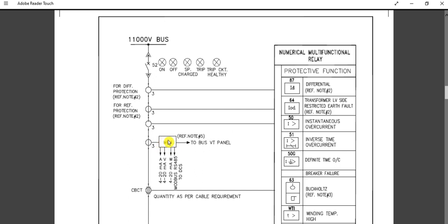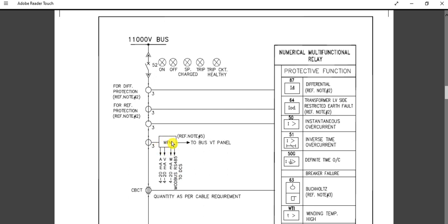The fourth CT is connected to the MFM — the digital multifunction meter. From this multifunction meter, a signal goes to the building services panel and also to a remote area for remote interface. An additional feature available here is Modbus RS485, which provides DCS connectivity. This unit communicates to the DCS for the parameters required to be displayed or maintained at the DCS.